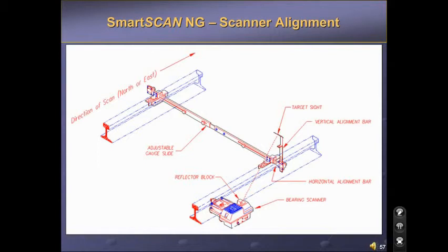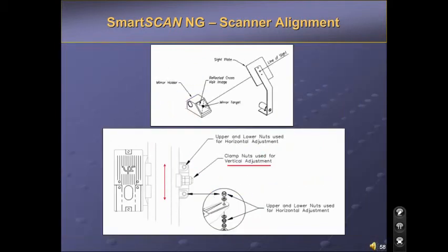It is not necessary to determine magnetic center on the transducers. Physical centering is acceptable. To see where the scanner is looking, look through the hole on the target sight and see if the X is in the circle. There are two adjustments to scanner alignment, a vertical adjustment and a horizontal adjustment.